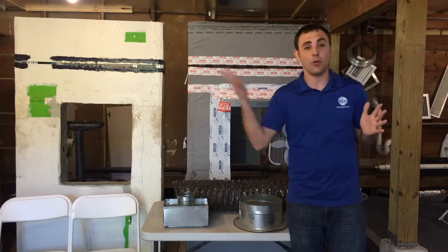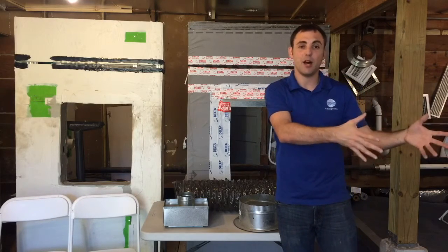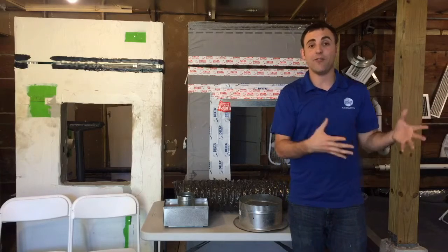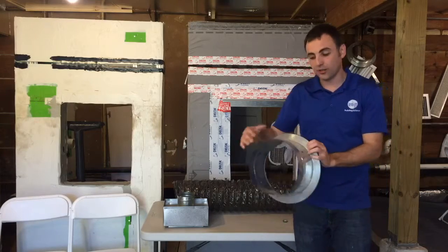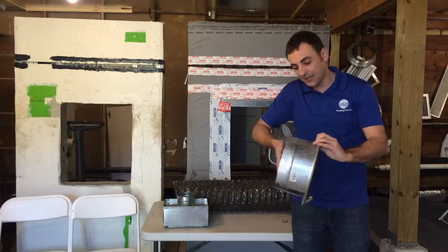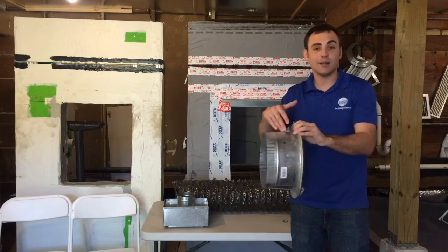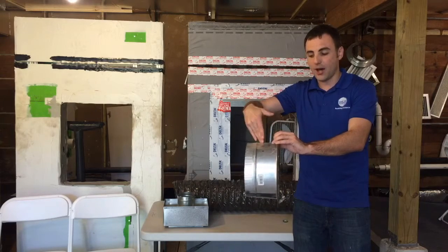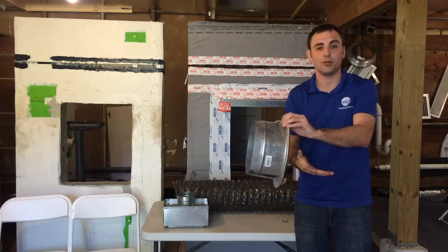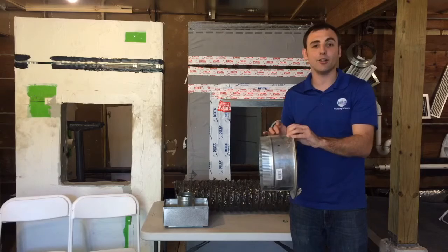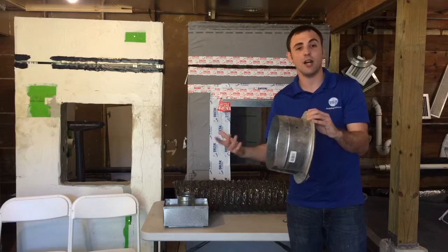So if you're looking at what we just saw a minute ago with a standard supply plenum, like a ductboard plenum coming off and then ducts going off of that, if that's your setup, you're going to want a damper at that plenum. So you've got starting collars like this that attach to the plenum, and inside here can be a movable damper. And this damper is the best place to control the airflow because it's right at the plenum. Any air that's going to get deflected is going to immediately go into another part of the duct, pressurizing the plenum some more, that sort of thing. So this is the ideal place to close off a vent, essentially increasing the velocity.